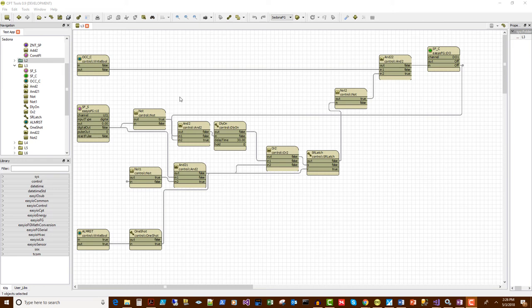Think about a supply fan, right? There are only so many ways to turn a supply fan on or off. And what I find with a lot of new programmers is that they spend a ton of time trying to figure out how to do maybe 4 or 5 tasks. They need to turn fans on and off. They need to switch between heating and cooling states. They need to open some valves. They need to open some dampers, and maybe they've got some lead lag switching or some staging. Those 5 or 6 real basic tasks are what you're going to spend the majority of your time on in your programs. So why not learn design patterns that show you how to write that code, and then you just reuse it again and again and again?